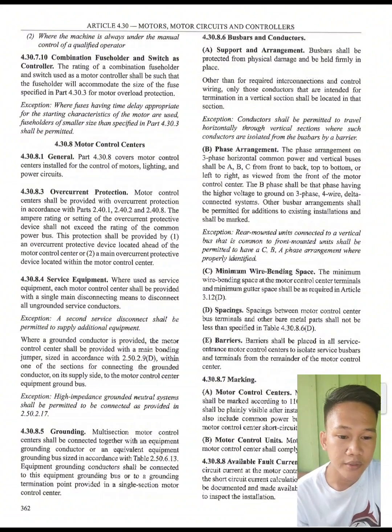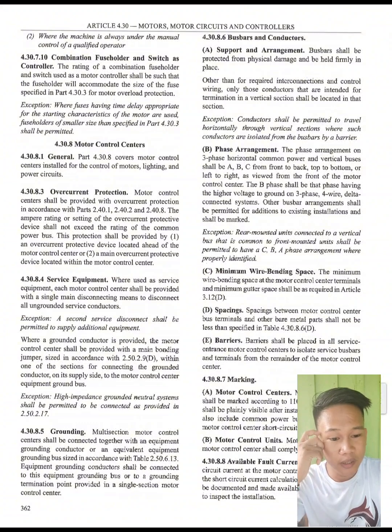So, we have here 4.30.8.6 Bus bars and conductors. A. Support and arrangement. Bus bars shall be protected from physical damage and be held firmly in place. So, this is so the bus bars cannot be damaged. Other than for required interconnections and control wiring, only those conductors that are intended for termination in a vertical section shall be located in that section. So, there is an exemption. Conductors shall be permitted to travel horizontally through vertical sections where such conductors are isolated from the bus bars by a barrier.